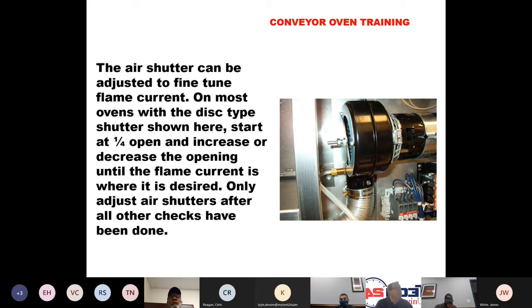The air shutter can be adjusted to fine-tune flame current on most ovens with a disc type, like that shown here. You're going to start at about a 1/4 inch open, and you can increase or decrease until your flame current's where it's desired. You should only adjust the air shutter after all the other checks we're going to talk about have been done. So air shutter fine tuning is the last thing we do. If we know that our burner and our igniter and our sensor are clean, we know we have a good ground circuit, we know we have good gas pressure, but all the other things have been checked. If you have low flame current, you can make some adjustments to an air shutter.